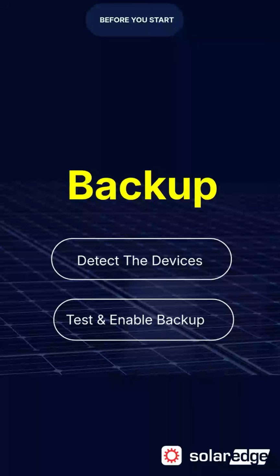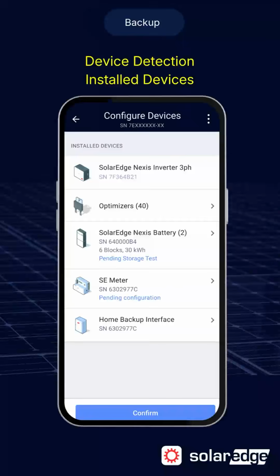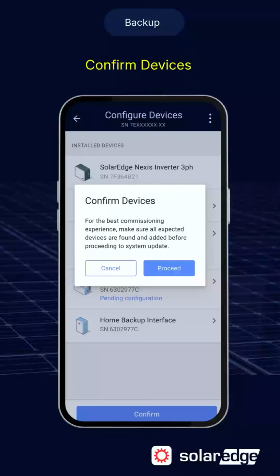Next, we'll run the storage test and configure the backup settings. Let's get started. Review the installed devices to confirm that all required backup system components have been detected. Verify that the battery, SE meter, and home backup interface are listed, then tap Confirm to continue. Before continuing, confirm that all expected devices have been detected. If everything looks correct, tap Proceed to continue with the backup commissioning process.